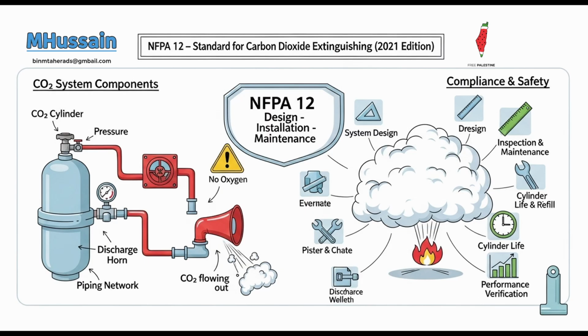And what about systems that were already there in those normally occupied spaces? What's also critical is how existing systems are handled. Existing total flooding CO2 systems in normally occupied enclosures were only permitted to continue operation if they were retrofitted with specific safety features by December 31st, 2008. A deadline. What features? These mandatory retrofits included system lockout valves, pneumatic pre-discharge alarms, and pneumatic time delays. Lockouts, alarms, delays. Got it.